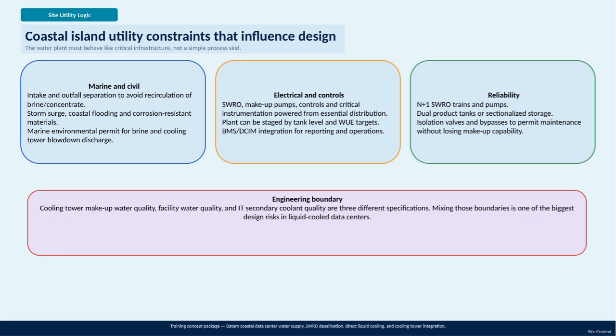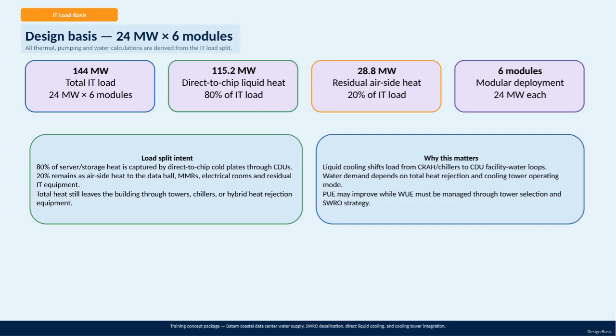Here, we're looking at the IT load basis, which forms the foundation for all our thermal, pumping, and water calculations. The design is based on a total IT load of 144 megawatts, divided into 6 modules of 24 megawatts each. This modular approach allows flexibility in deployment and management. Of the total 144 megawatts, about 80% or 115.2 megawatts is managed through direct-to-chip liquid cooling. This means a majority of the heat generated by servers and storage is captured directly at the chip level using cold plates and cooling distribution units, or CDUs.